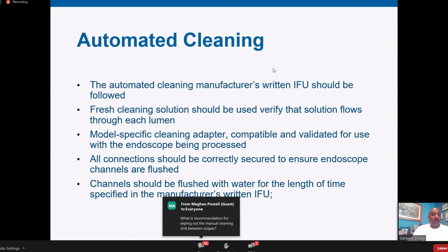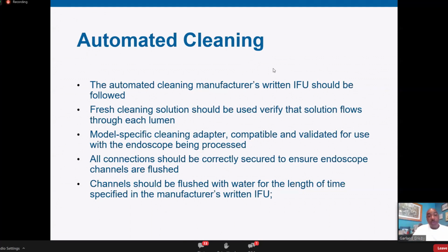All right. Now moving on to automated cleaning. One of the questions was about automated cleaning too. Automated cleaning manufacturers' written IFU should be followed. I know some folks have seen some where they say, just do this, but don't do that. There's a slide in here that talks about when one piece of equipment disagrees with the other. We'll discuss that later. Fresh cleaning solution should be used to verify the solution flows through each lumen as far as automated cleaning is concerned. Model-specific cleaning adapters compatible for that particular scope that you are using.